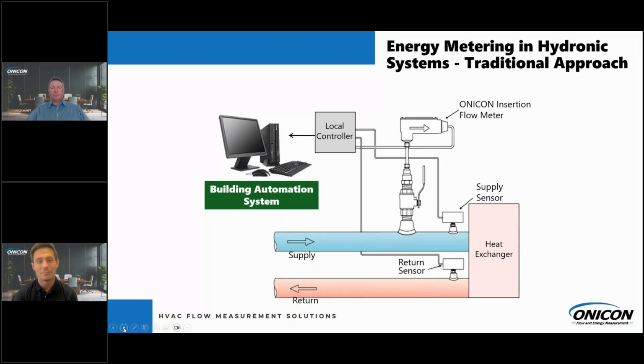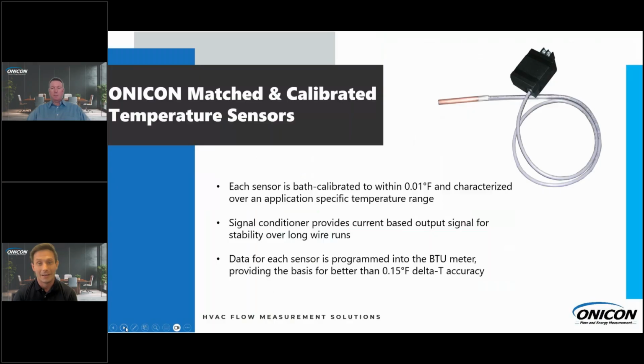The first area we looked at was the temperature sensors. We realized the temperature sensors they were using, the Platinum Class A RTDs, weren't very accurate. They had a high margin of error that was affecting the calculation, which inspired us to create our own ONICON temperature sensor. This is a match paired calibrated temperature sensor.